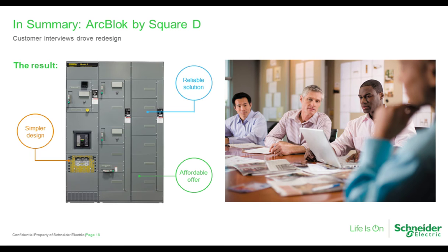Our ArcBlok technology redefined the equipment construction to play an important role for personnel and equipment protection. It will also make the selection of arc flash reduction methods easier for everybody, like specifiers, designers, and end users. We used a safety by design approach. Here are some recommendations to consider while selecting arc flash mitigation techniques for your system. First, you need to reduce arc flash incident energy level or PPE as much as possible, and you need to improve your service continuity. You may use some other techniques, but if your equipment is damaged, it may cause a service continuity problem.